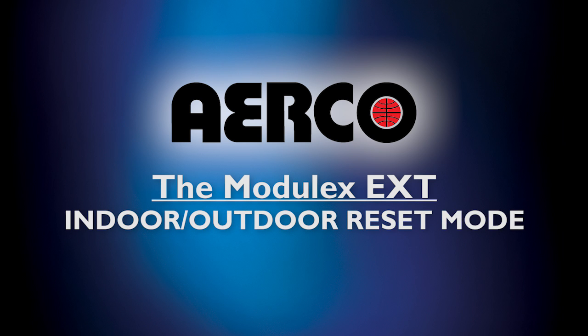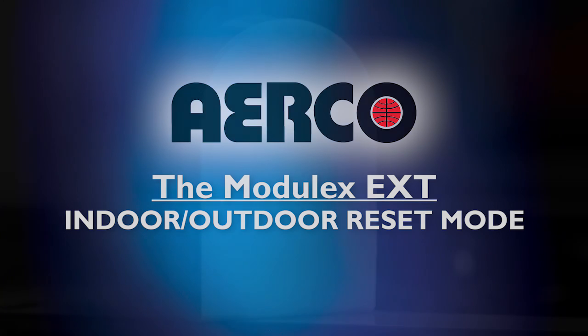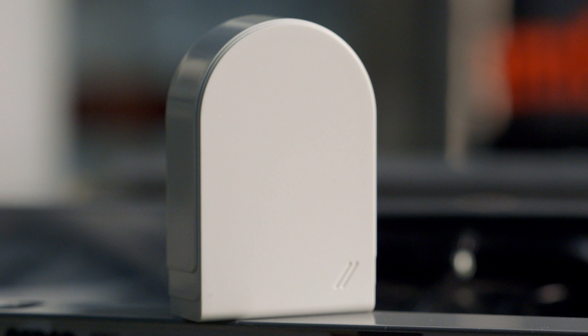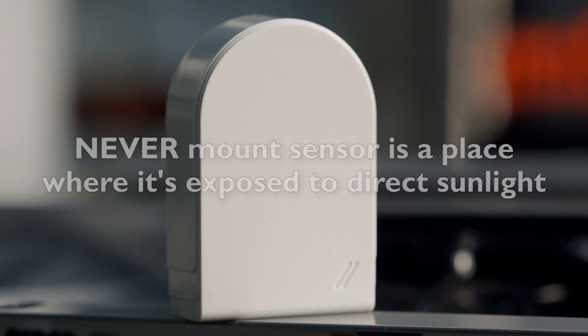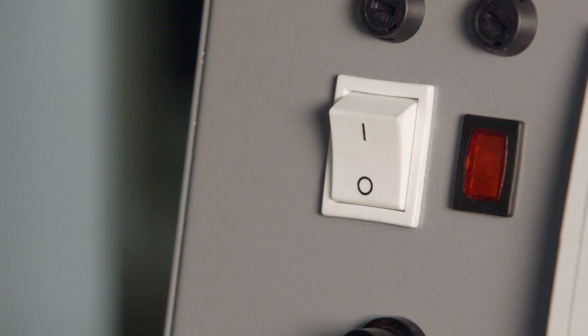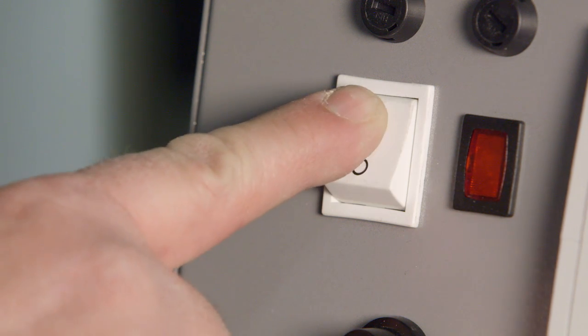To set up for indoor-outdoor reset mode, take the following steps as demonstrated here. Your unit was accompanied by an outdoor air sensor. It should be mounted on the outer north or northeast side of your building, away from windows, doors, and vents. Never mount the sensor in a place where it's exposed to direct sunlight. Start by making sure that the on-off switch on the front of your Modulex boiler is on.